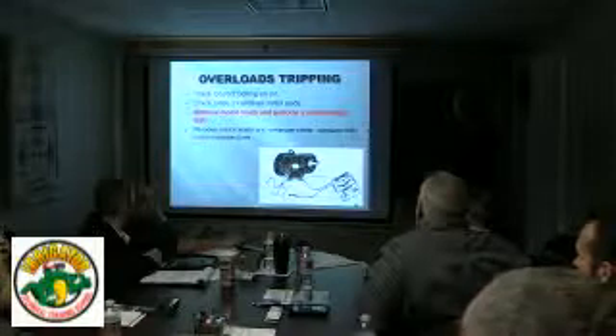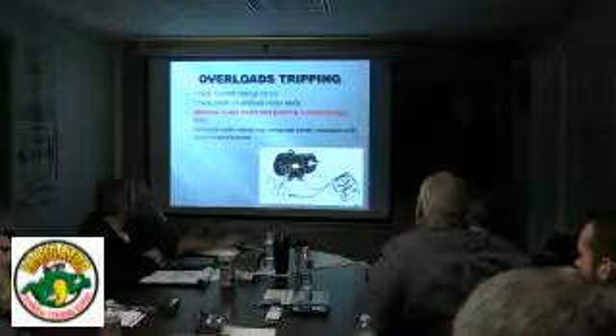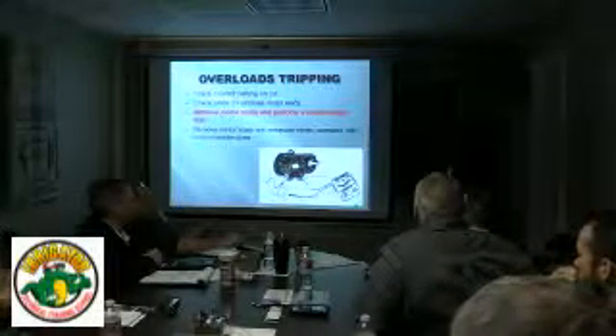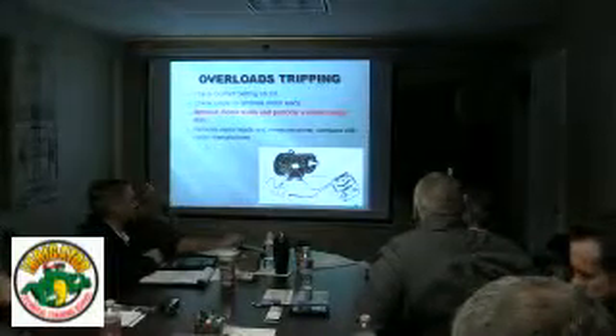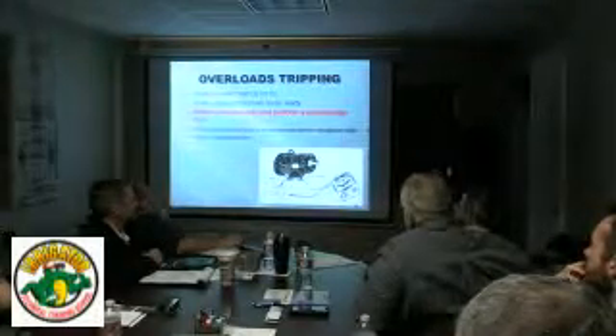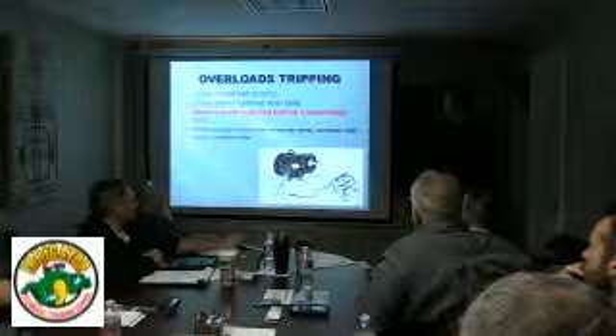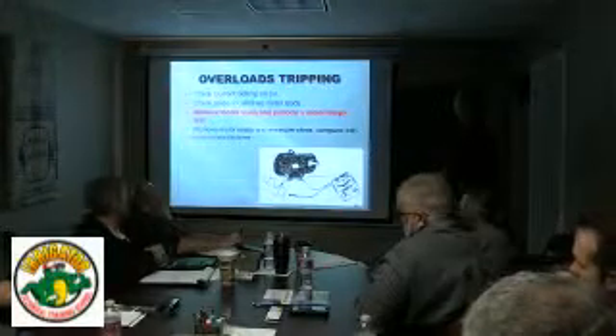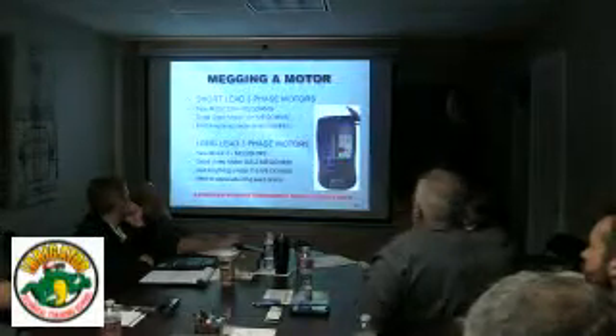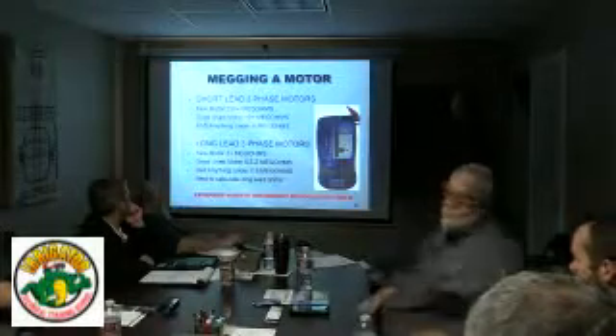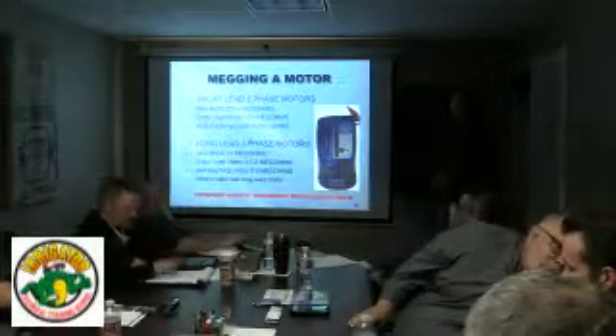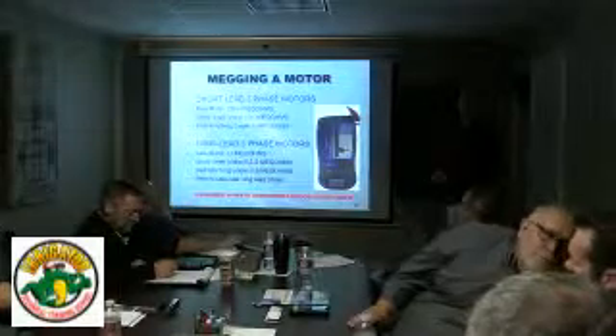You check it from each input lead of the drive to ground to do a motor meg test. And what that's doing is it's testing the insulation of that motor to see if there's any breakdown in it, any leakage to ground. So you apply a high voltage to the motor windings. If they are breaking down, it's going to leak through there and go to ground, and the megger will pick it up. Also, remove motor leads and measure with ohms. These are just some examples of what you might see with the megger.